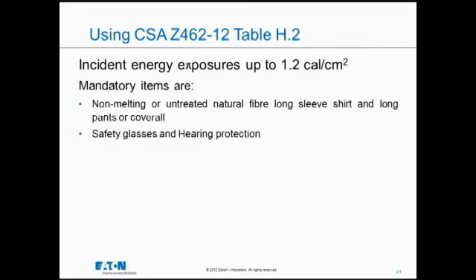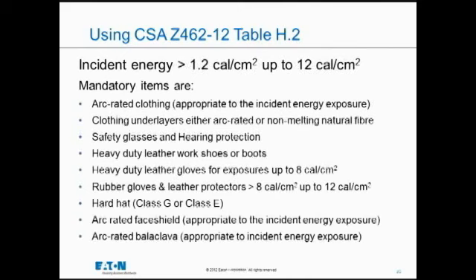The next level that we're using in 2012 is between 1.2 and 12 calories, and there's a list of items that are mandatory. You must wear all of those items, and the big news this year is balaclava. It's shown at the very bottom of this table. Balaclava was the last piece of the puzzle to protect more or less the back of the head from an arc flash hazard. We were not providing any protection to the back of the head with a face shield, and now it's a face shield and a balaclava together.